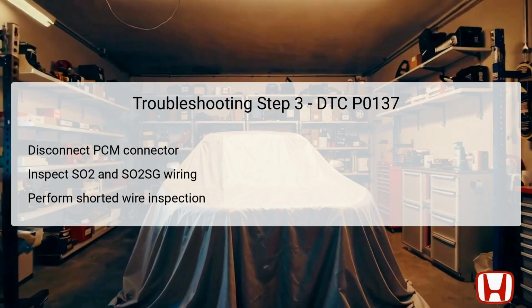It is essential that both SO2 and SO2SG read more than 1 megaohm, indicating they are functioning correctly without defects. Should any abnormalities be found during this wire inspection, further action is needed to repair or replace faulty wiring to resolve the issue.